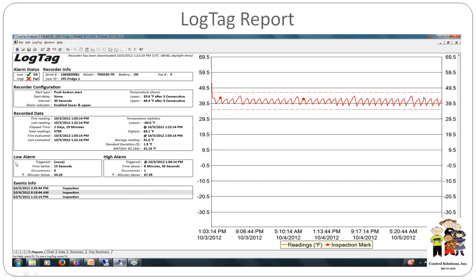Down below, my low alarm and high alarm give a total value - I was 8 minutes and 45 seconds out of tolerance, with one alarm. Over here, I unplugged the logger and was about 15 seconds away from my desk.